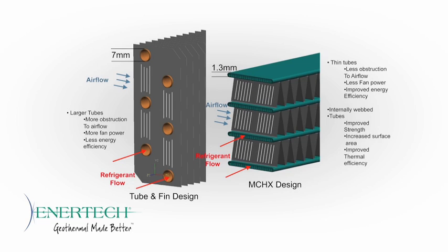When looking at the design of the micro-channel coil, the advantage over current tube-and-fin coils becomes very apparent. Where standard coils use large tubes to carry refrigerant through the fin pack, the micro-channel coil utilizes hundreds of smaller channels arrayed within the coil to do the same job. Because the circuitry is more evenly distributed, the refrigerant flows more naturally and the channels don't restrict airflow. Add the true metal-to-metal bonding of the fin pack to the distribution channels, and you have even better heat transfer.